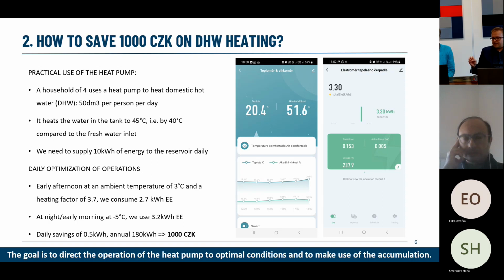Let's leverage. Let's heat up the hot water storage. Let's accumulate cold in the building. It's totally fine because the thermal constant is great for the buildings, and you don't have to pump the heat or the cold constantly at any given time, but you can allow a bit of a swing of the temperature so that it is not bound to maintain a constant 21 degrees C inside temperature with tolerance of 0.1. But if you let an interval of 20 to 22, somehow the control system can start leveraging more effectively that the outside temperature, the ambient temperature is favorable. So I start producing cold or heat, whatever is the medium, and I leverage the favorable conditions.